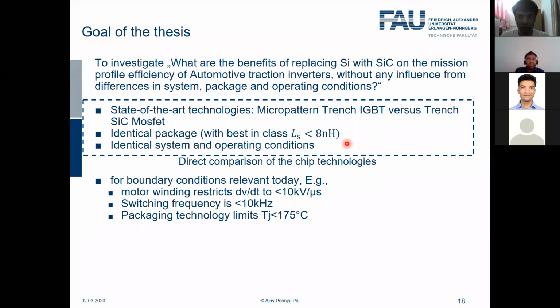And the second thing is we have to consider boundary conditions which are relevant today. For example, we know that the motors of the electric vehicles, the windings of the motors, restrict the switching speed to less than 10 kilovolt per microsecond, maybe 15 kilovolt per microsecond. And this is a fact today. So therefore, we have to take this also into account.